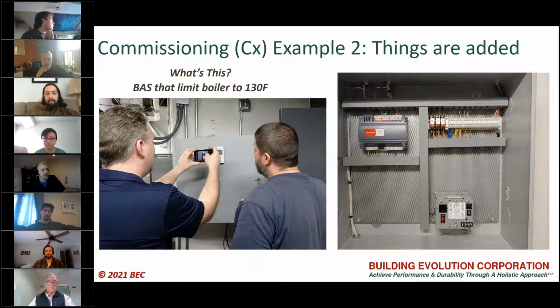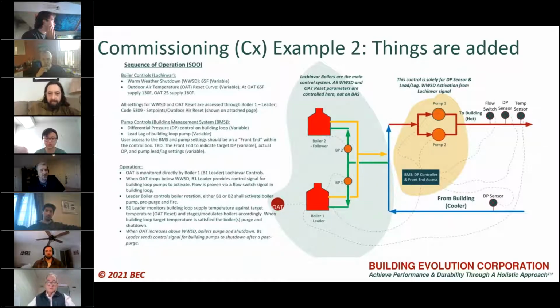Part of this was that the actual design didn't really have a sequence of operations. So in all fairness to the contractor, they came up with their own to get the building to work. But we just sat there and sketched it out with them, what they actually needed to do to get the Lochinvar boilers to take over control of their pumps, basically flip the control.